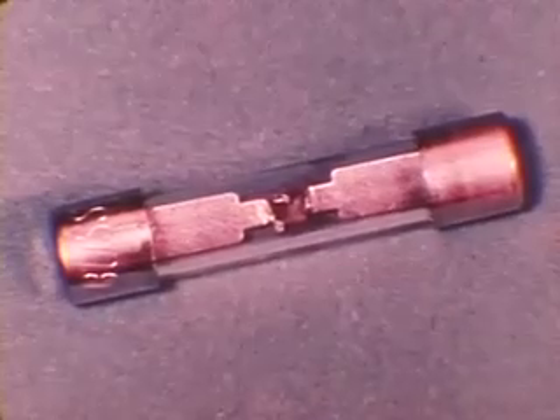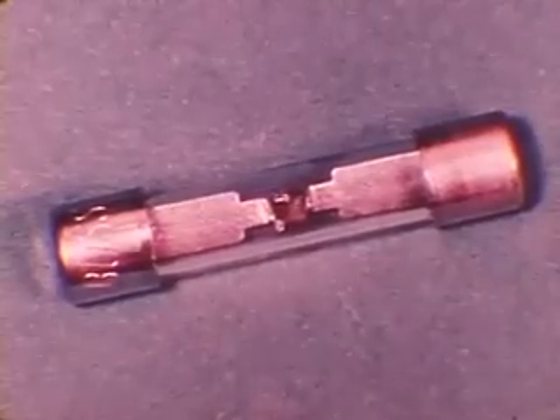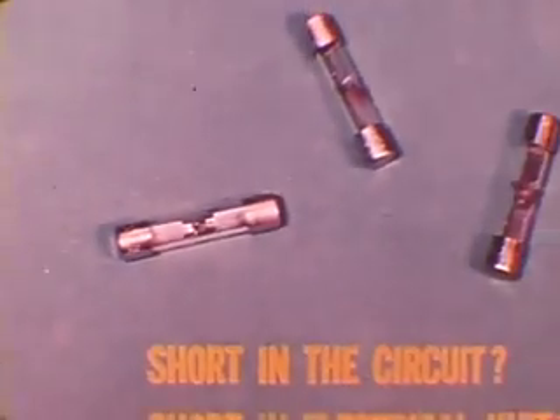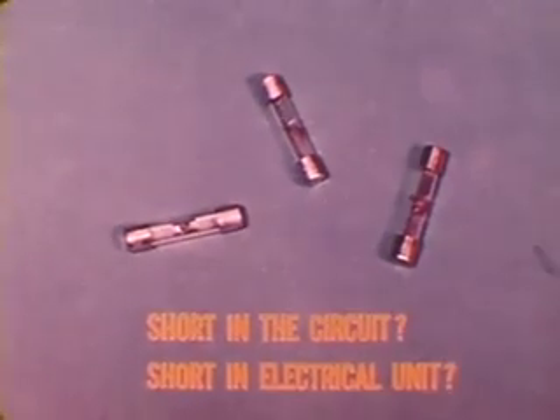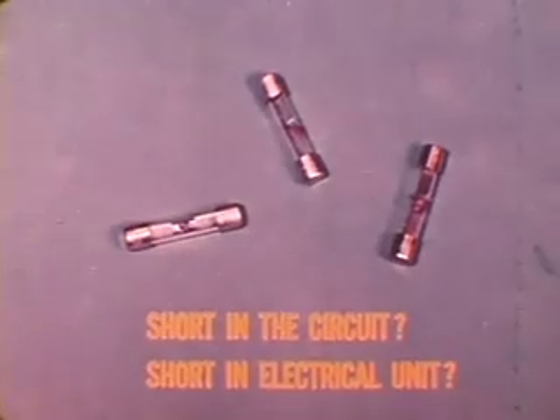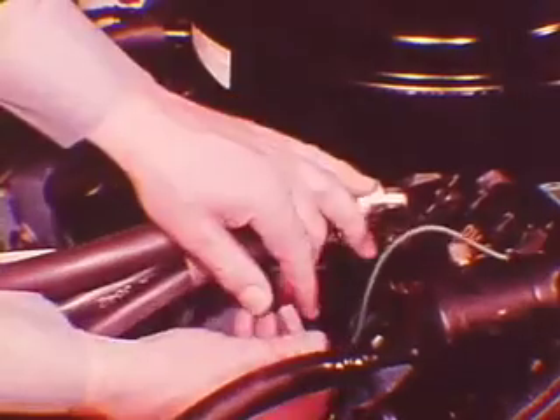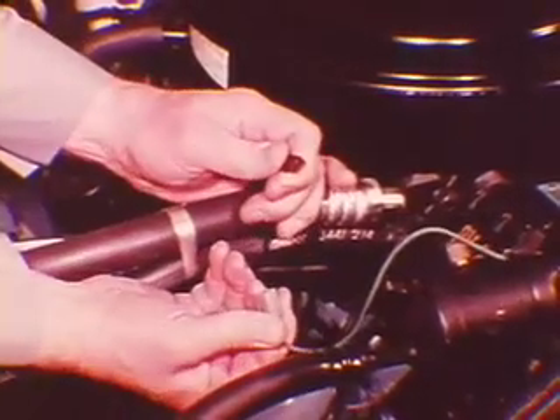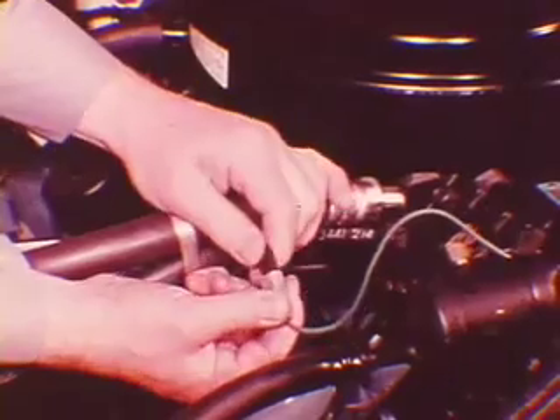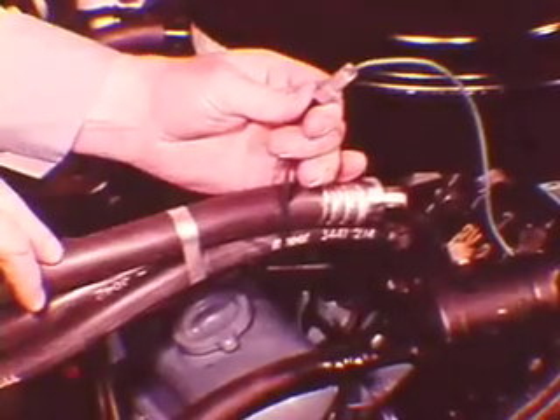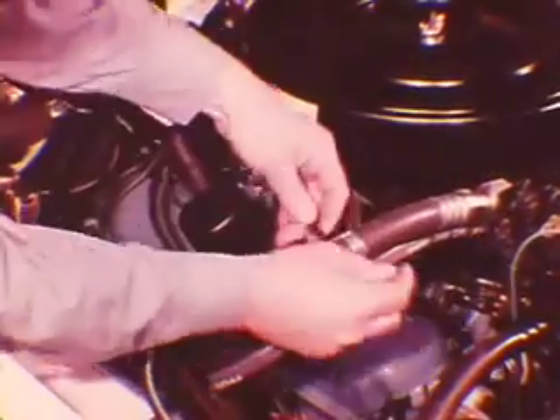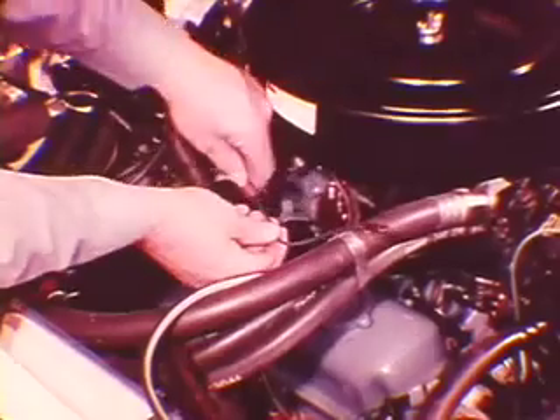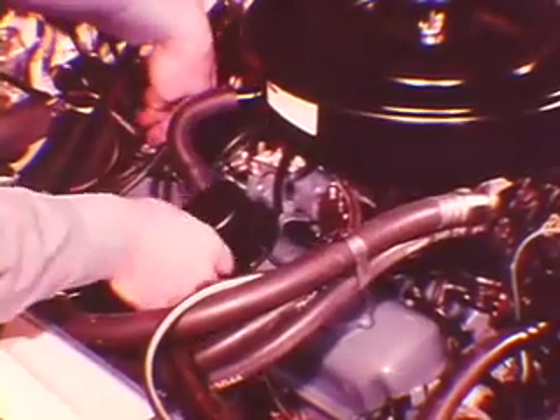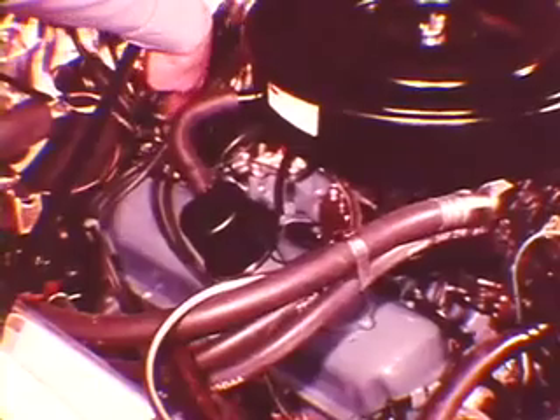The second basic kind of problem is a short circuit that keeps blowing fuses or causes a circuit breaker to open. This could be a short to ground in the circuit itself, or the electrical unit served by that circuit could be shorted. In a case like this, the first step is to disconnect the unit served by the circuit. If the circuit breaker stops cycling, or a new fuse doesn't blow, the trouble is in the unit and not in the circuit. However, if disconnecting the unit doesn't solve the short circuit problem, the trouble is in the circuit itself. Chances are there's a short to ground somewhere along the line.